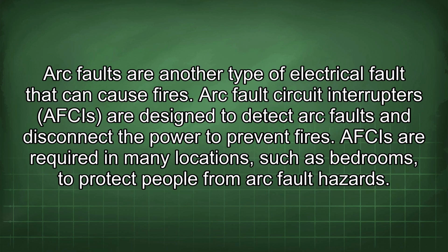Arc faults are another type of electrical fault that can cause fires. Arc fault circuit interrupters (AFCIs) are designed to detect arc faults and disconnect the power to prevent fires. AFCIs are required in many locations, such as bedrooms, to protect people from arc fault hazards.